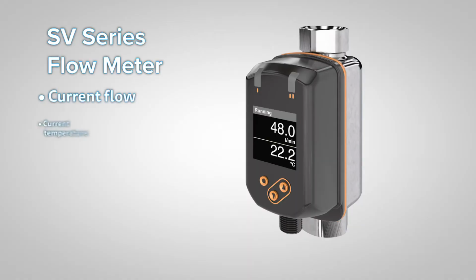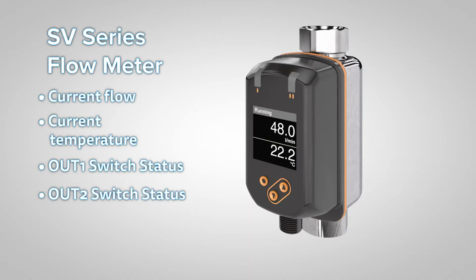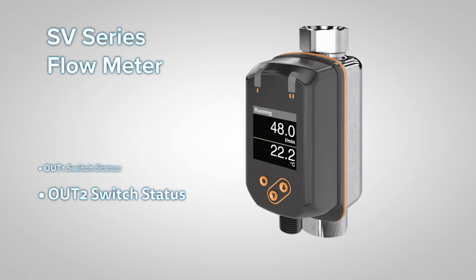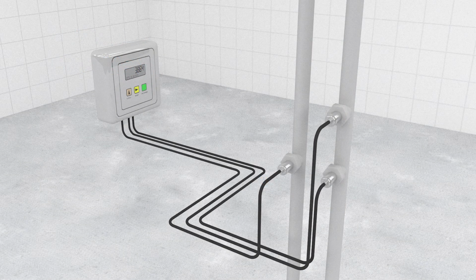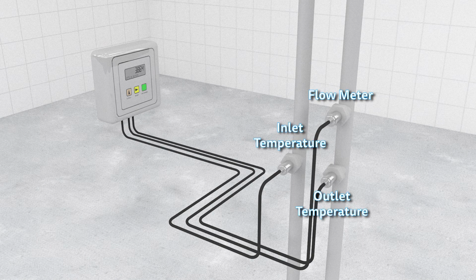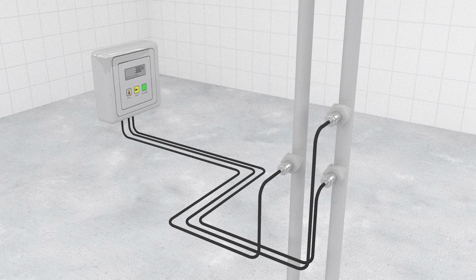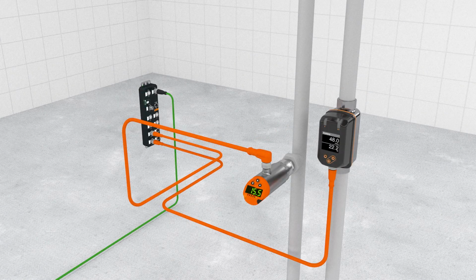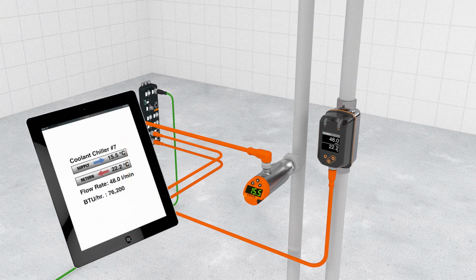Sensors today are combining various sensing values, and this opens the possibility to use these measurements for extended purposes. For example, monitoring the BTU of a chilled water system would require a flow meter and a temperature reading on the inlet and the outlet. This requires 3 different sensors and values. With IO-Link, a single flow meter can provide multiple process values such as flow and temperature over a standard 3-wire cable. IO-Link reduces hardware, wiring, and programming costs by up to 40% over traditional solutions.